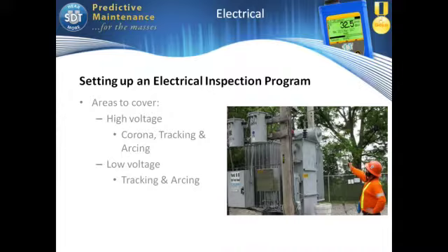Problems like corona and tracking are big problems on high voltage switchgear, but they don't generate heat, so you will not find corona and tracking with an infrared camera. You can see corona with an ultraviolet camera for sure, but the same equipment you're using for all your other airborne ultrasound applications, you can take outside and listen to your high voltage switchgear with.